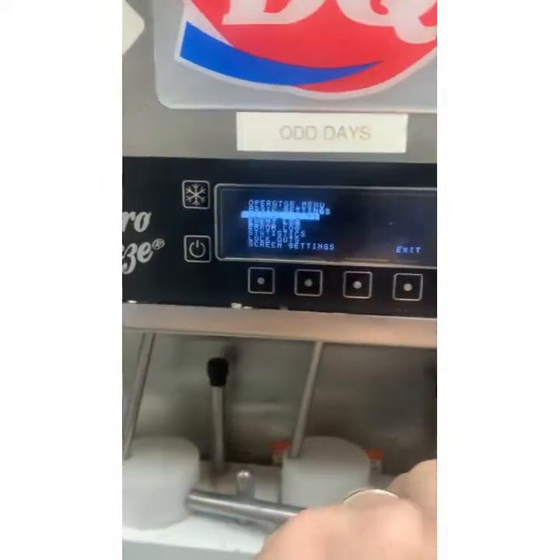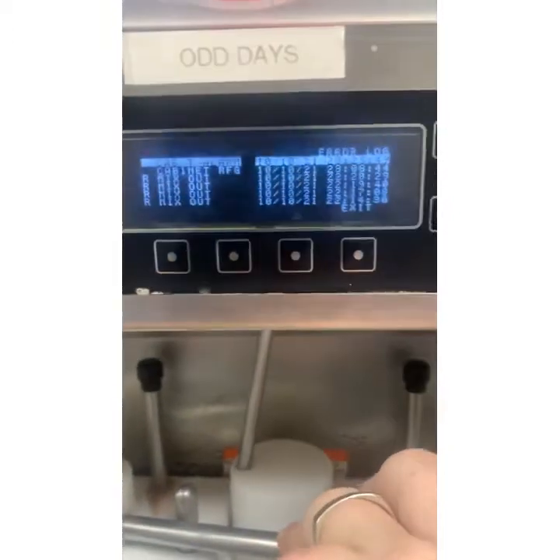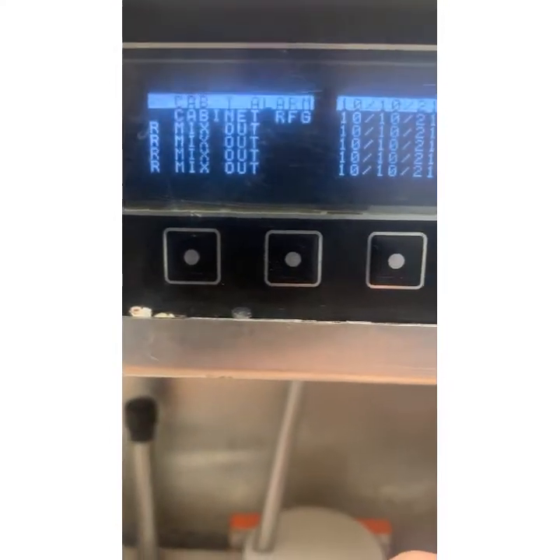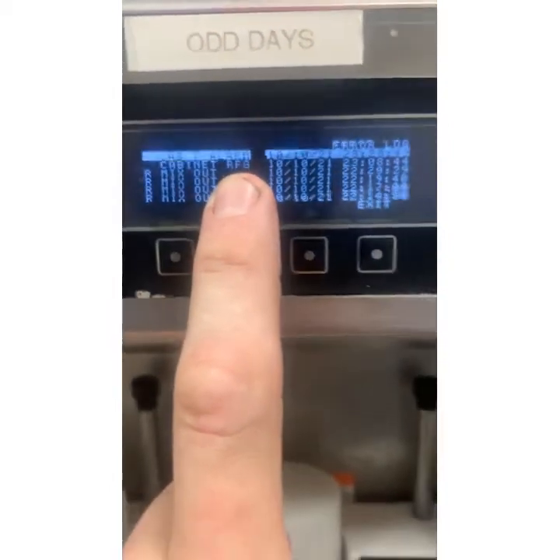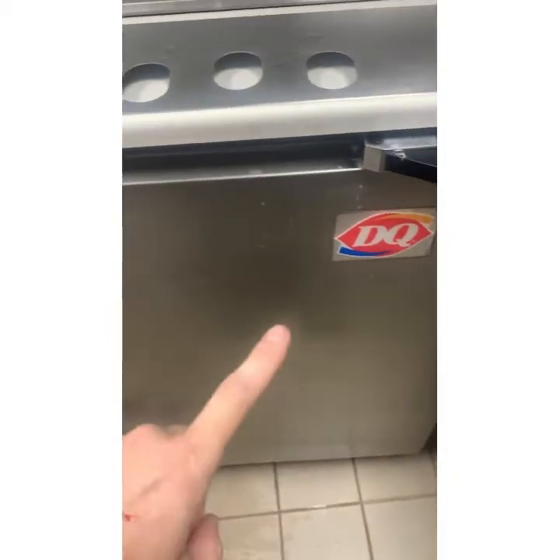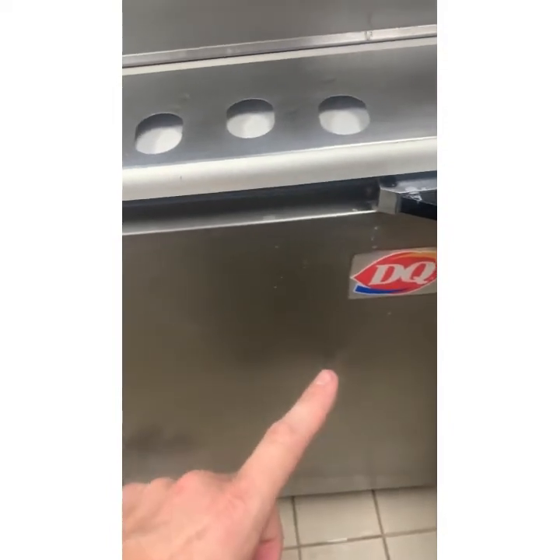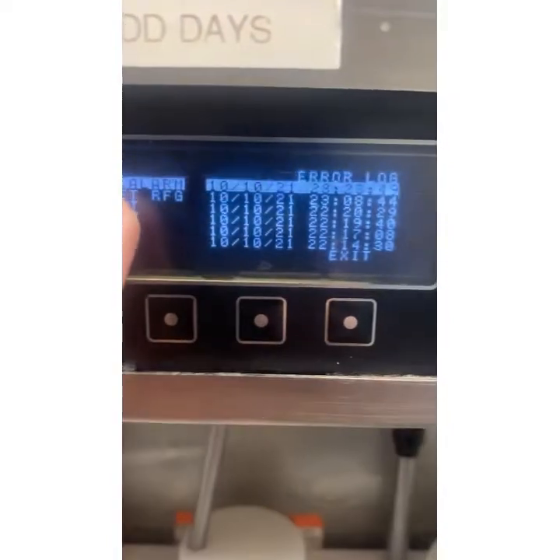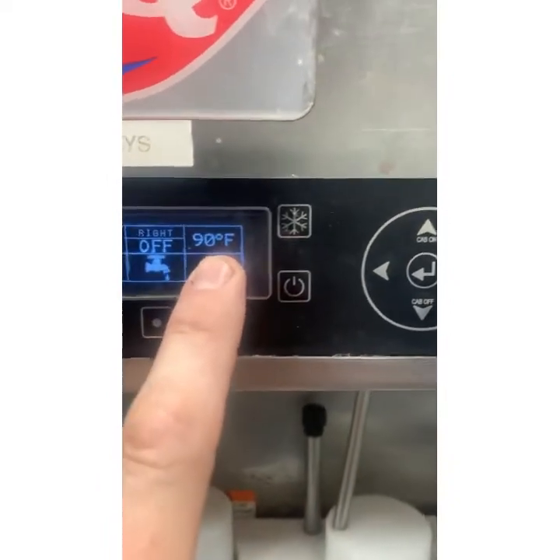So when I got here, I'm under the error log, and you're going to see a temp alarm, cabinet refrigeration. Cabinet refrigeration means the cabinet compressor has been running for 90 minutes and hasn't satisfied. So that's a problem. The temp alarm shows you that the cabinet's too hot. Now if I exit all this out, it's 90 degrees in that cabinet.